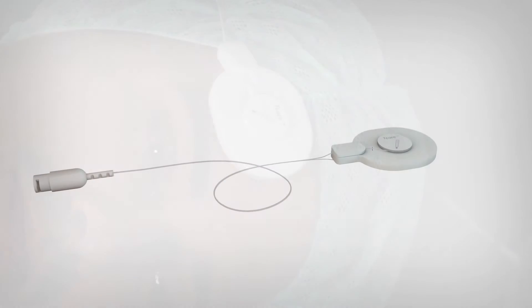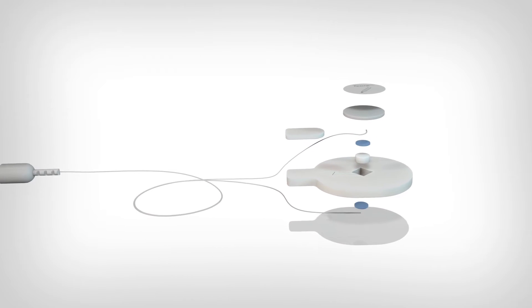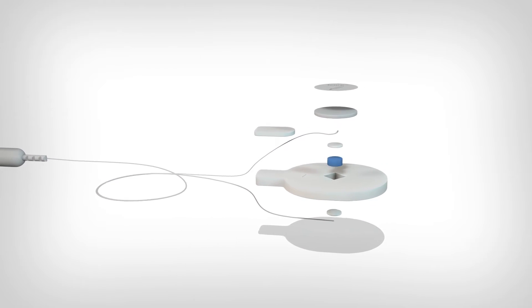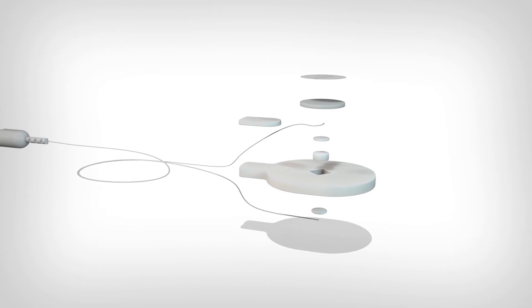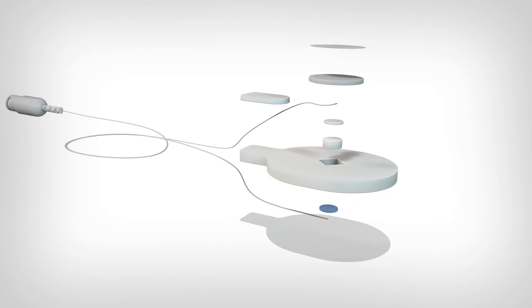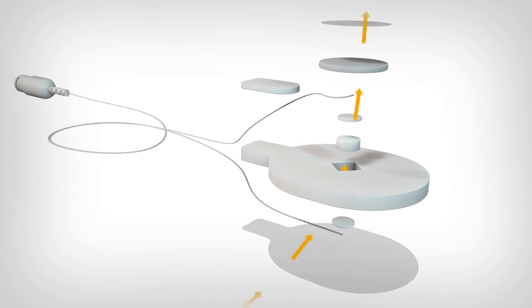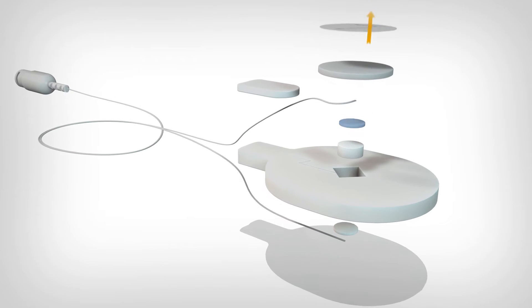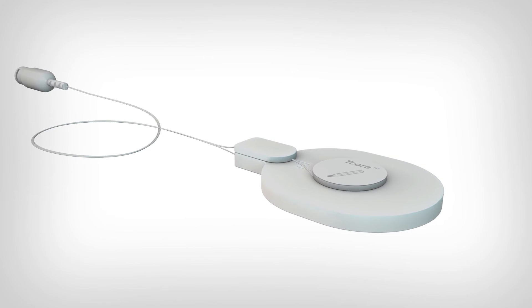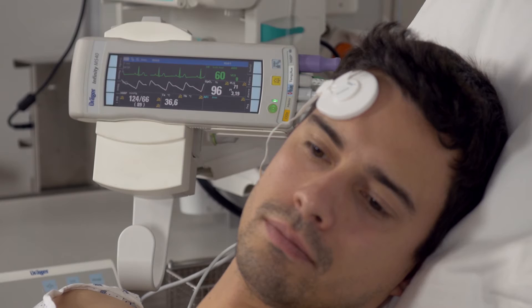How does this sensor work? The Dräger T-core sensor consists of two separate temperature sensors separated by an insulating layer. This so-called double sensor is applied to the forehead of the patient. While one sensor measures the temperature near the surface of the skin, the other measures the flow of heat to the environment. With this information, the T-core adapter calculates the body temperature close to the core and transmits the data to the patient monitor.